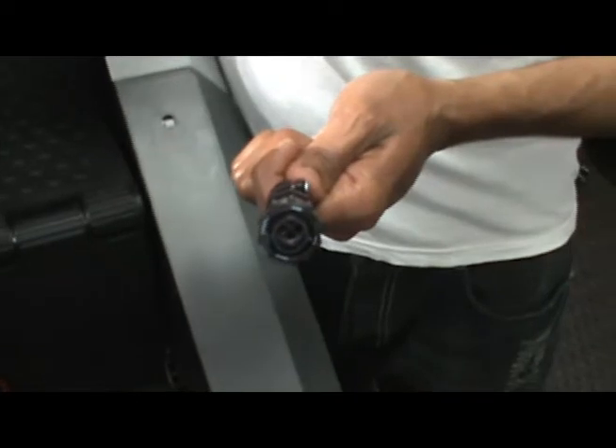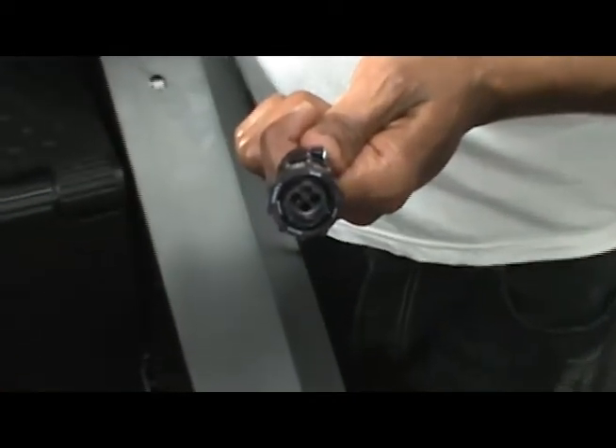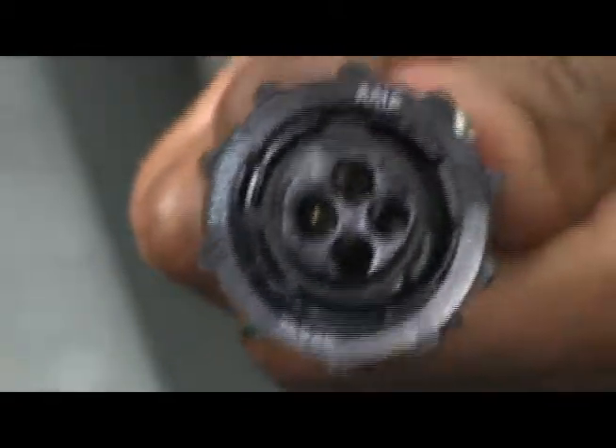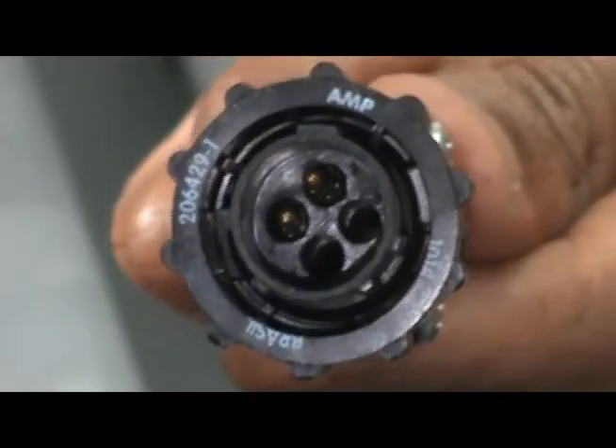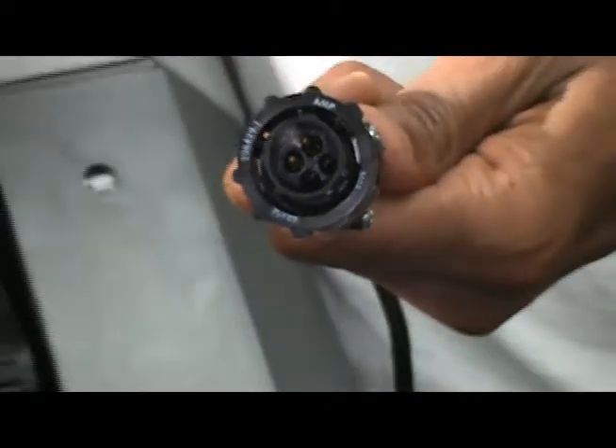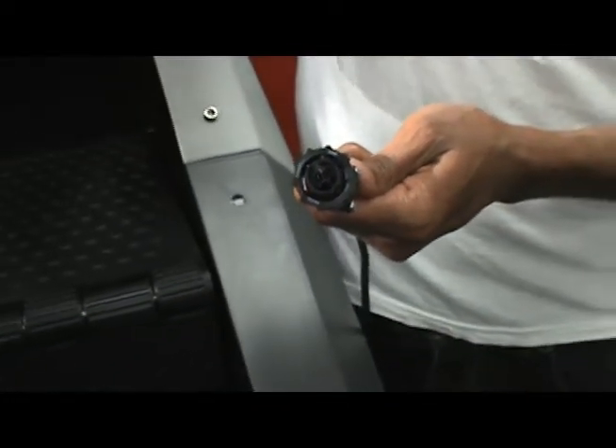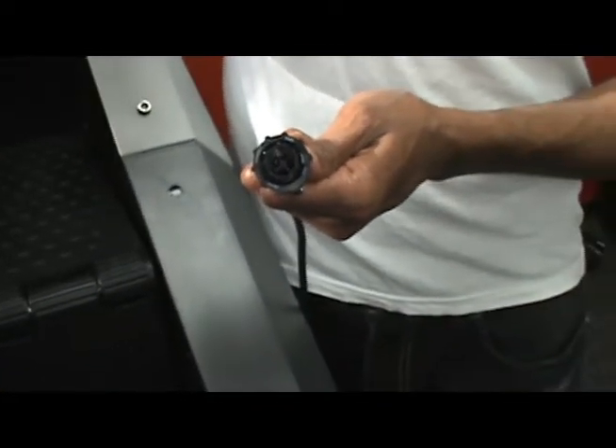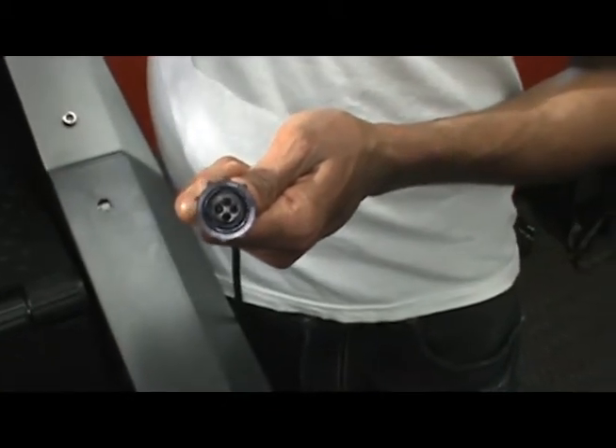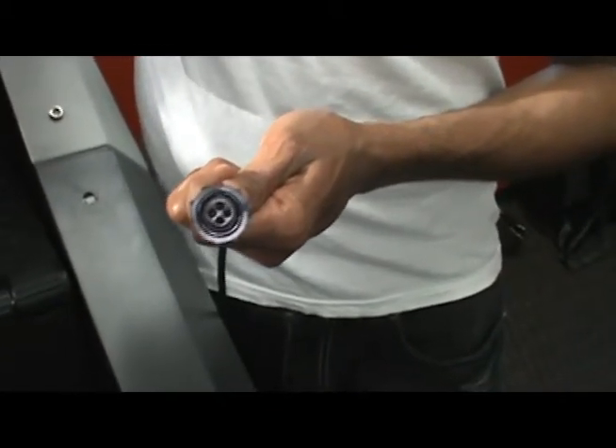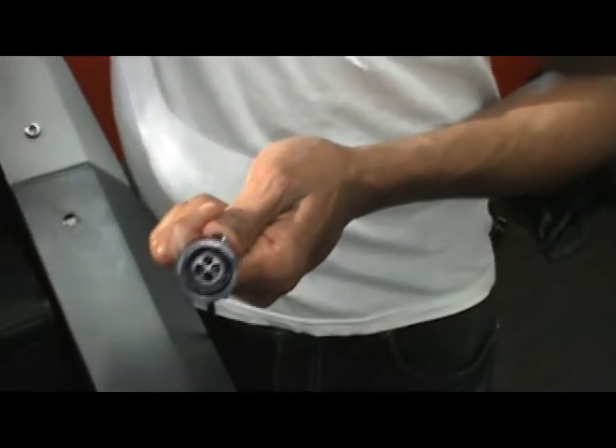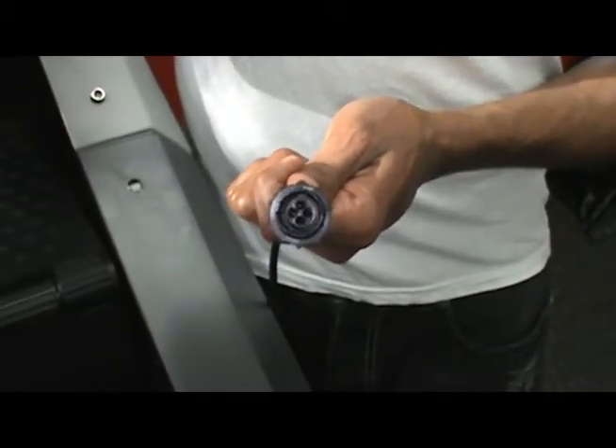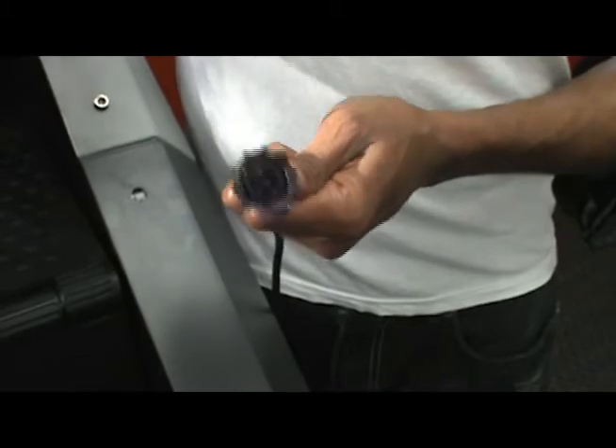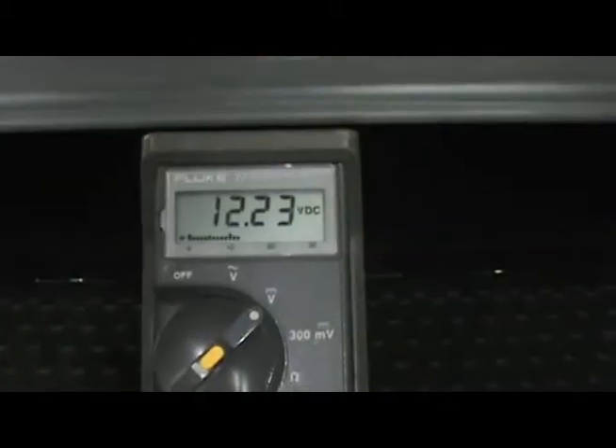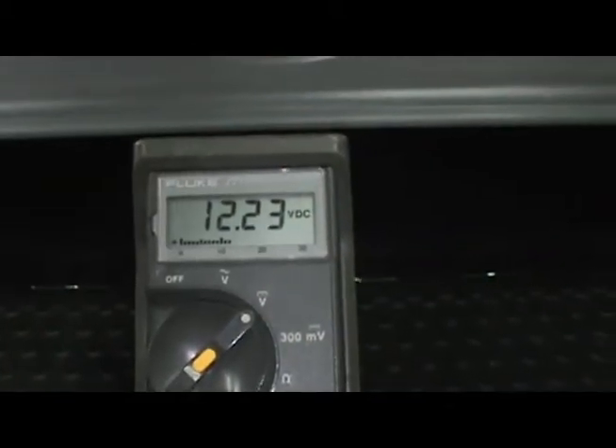Now that we have it unplugged from the machine, inside this connector you'll see two metal prongs sticking out. We'll use our multimeter to do a DC voltage check on those two prongs. You want to be careful when doing this so you don't short anything out while sticking the prongs into the connector. We're looking for at least about 12 volts DC. As you can see right here, we have 12.2 volts, which is pretty good.